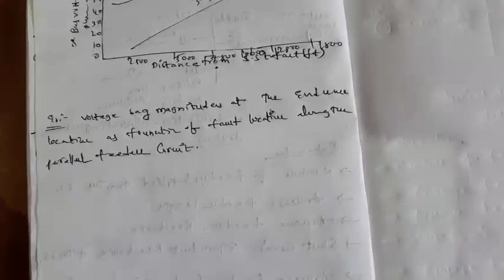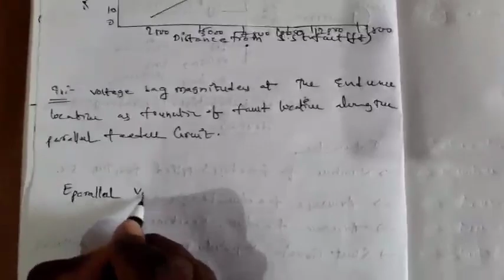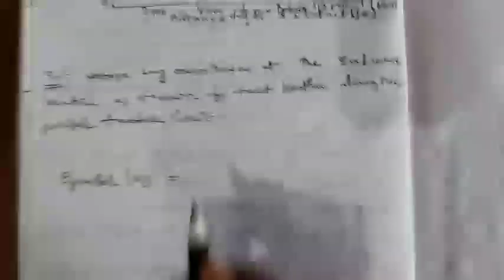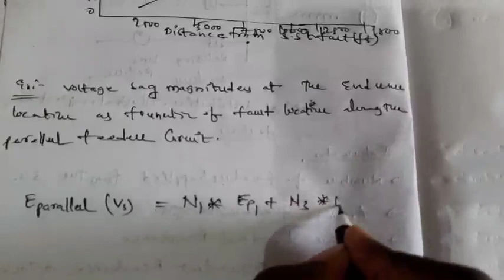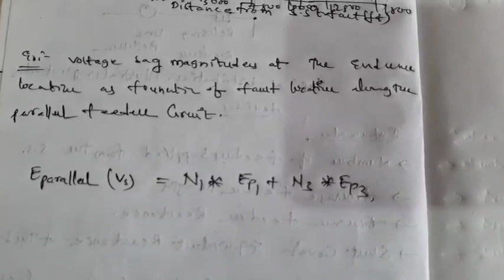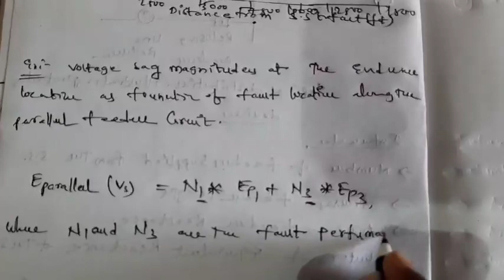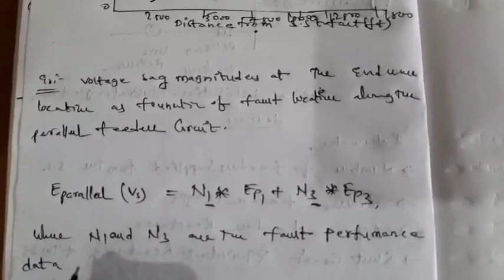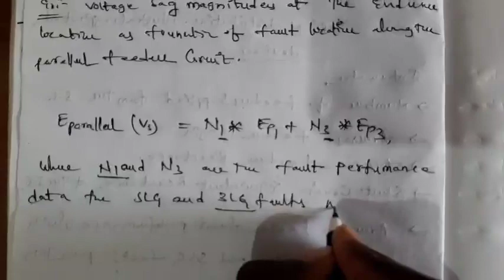Now, the voltage sag sensitivity of the equipment, that is, the minimum voltage rate, can be computed. That means the minimum voltage that can be withstood is computed as ES equals N1 multiplied by EP1 plus N3 multiplied by EP3, where N1 and N3 are the fault performance data of single line to ground and three-phase faults. 1 indicates single line, 3 indicates three-phase. N1 indicates single line to ground and N3 indicates three line to ground faults, in faults per kilometer per month.